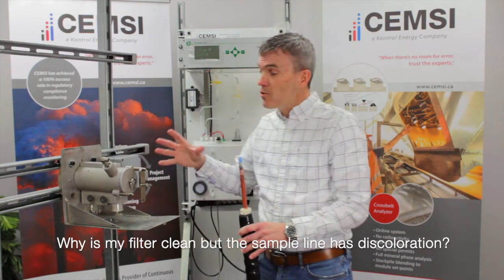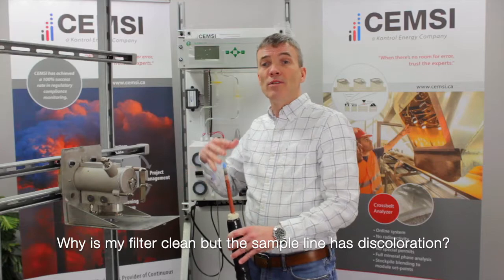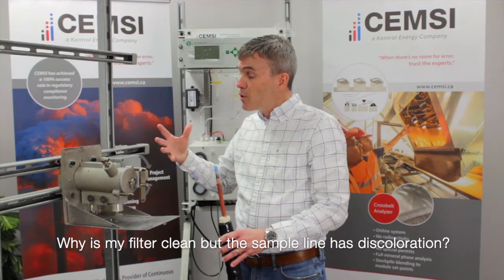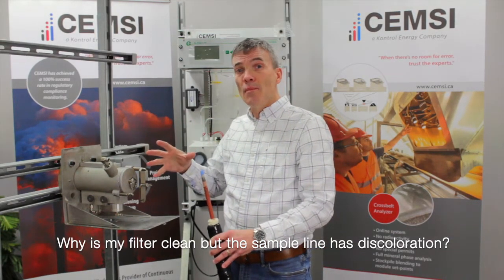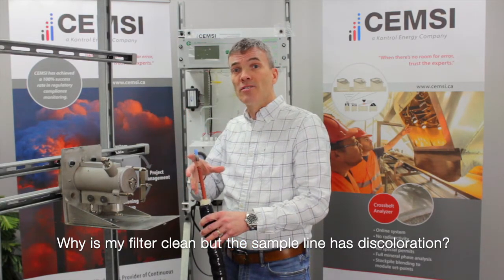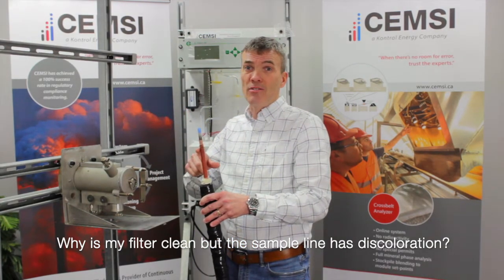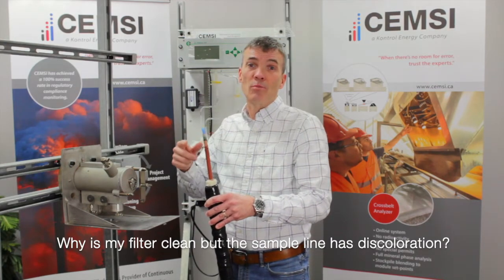So remember, in all of this, we're always dealing with chemical reactions. We're always dealing with time, temperature, and some sort of movement. So by controlling those temperatures, we control where this chemical knocks out. The most important thing is you don't want to knock it out in the sample line, because the sample line is one of the weakest points in the entire system.